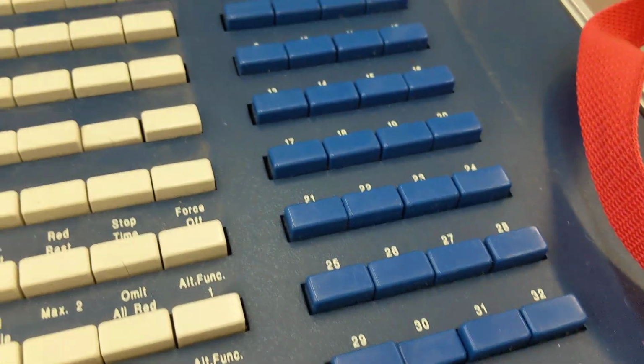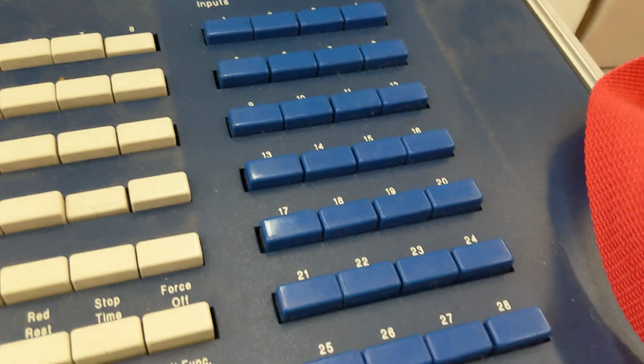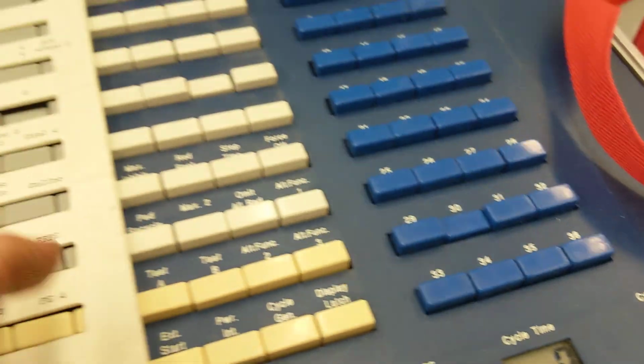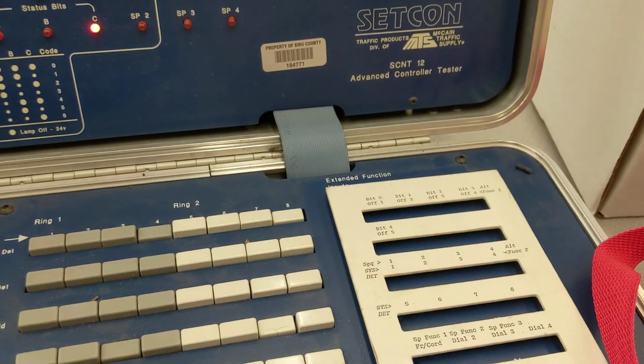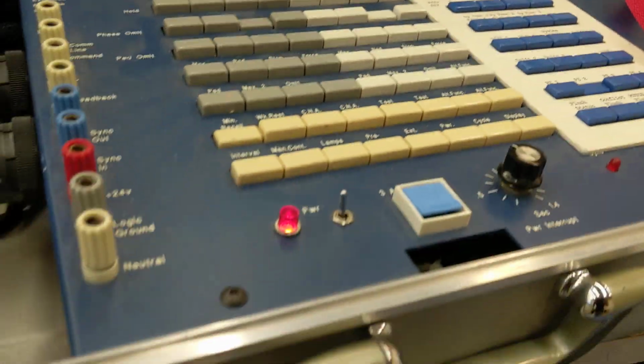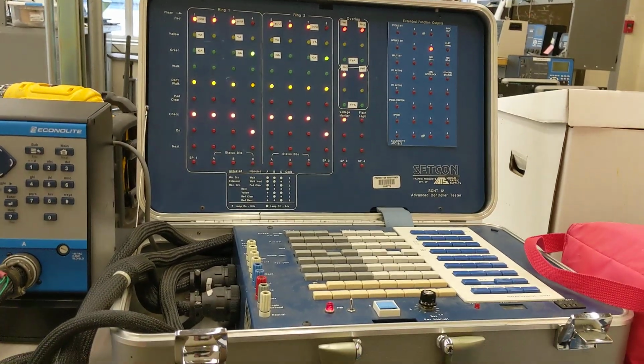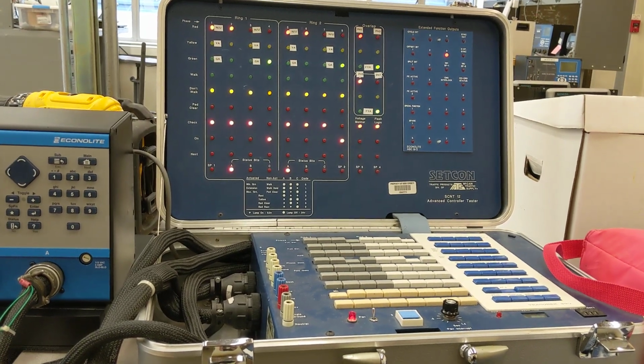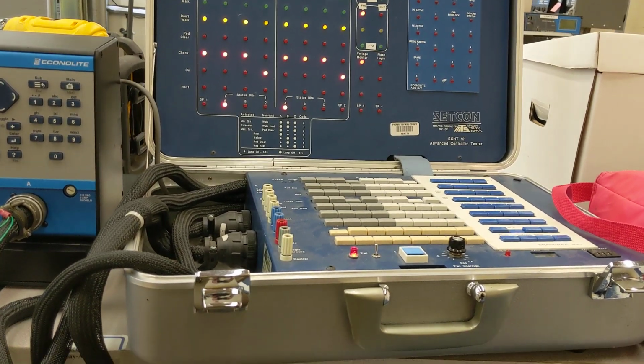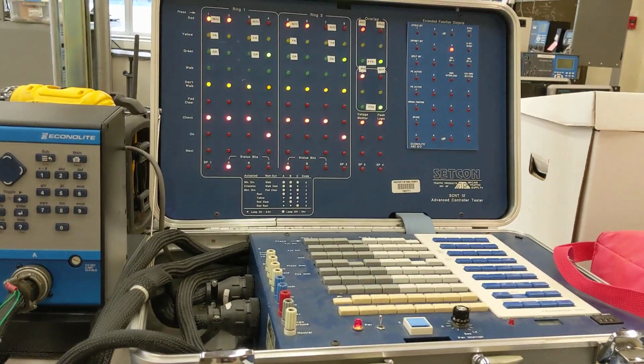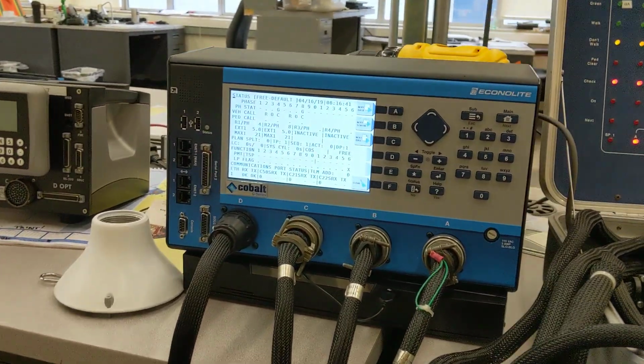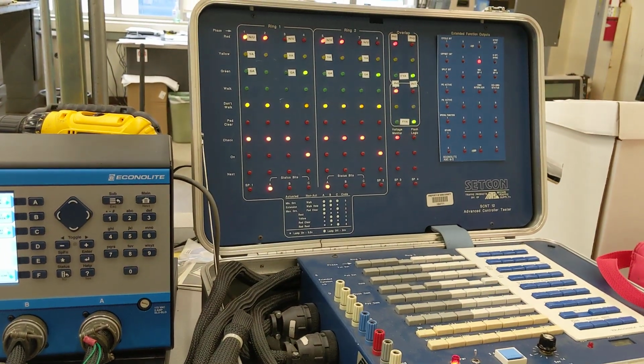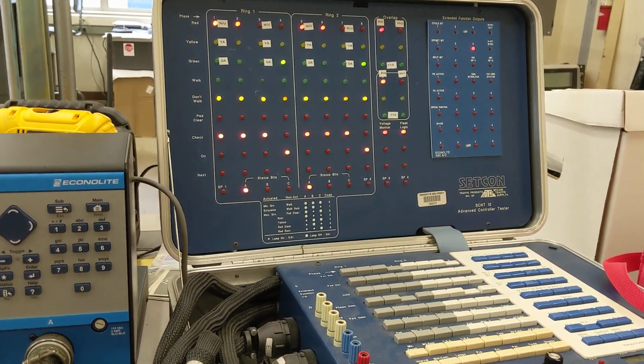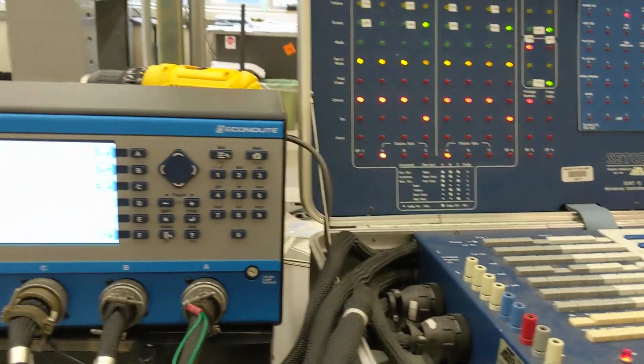But these are all just inputs, and it just depends on how those inputs are wired on the inputs and outputs as they come from the controller here, all jive with this guy here. And so let's just pretend that this was a TS1 cabinet, all would be good, and this is how this would run. But if you're running TS2 programming, obviously you can mock it up in here and just let your basic timings run, and that way you figure out you got your logic squared away.